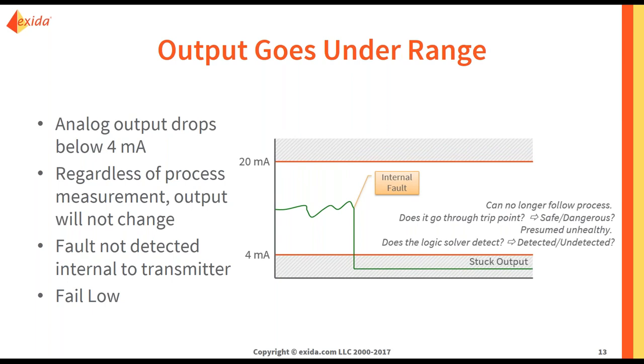Now let's say your output goes under range — it drops to below 4 milliamps. Regardless of the process measurement, the output will not change, so it is no longer following your process. The fault is not detected internal to the transmitter in this case. This is what we call a fail low. Again, we don't know if it is safe, dangerous, detected, or undetected yet. But we do know it can no longer respond to a hazardous scenario.